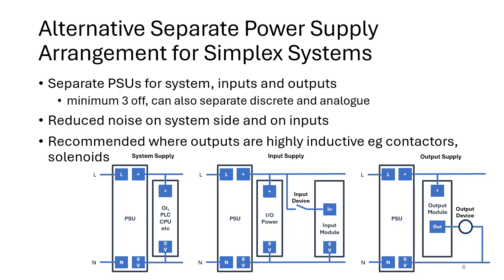So more power supplies, not too much more complexity. Again, you might want to tie the 0 volts together, or you might be relying just on the earthing and protection you have from the isolation of each device. So some of this is going to be application dependent, but this isn't going to cost too much more, and it's not going to complicate your wiring too much more, but it does give you quite a lot of benefits in terms of segregation for noise, as well as possibly reducing the overall size of each individual power supply, even if you need more of them in total.